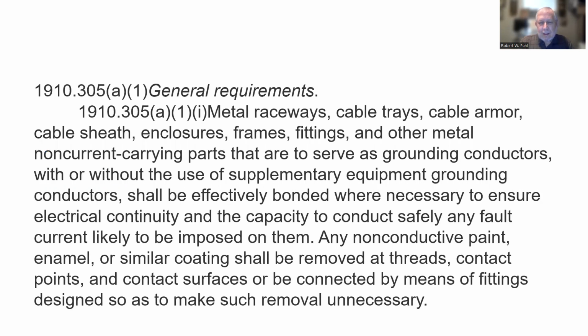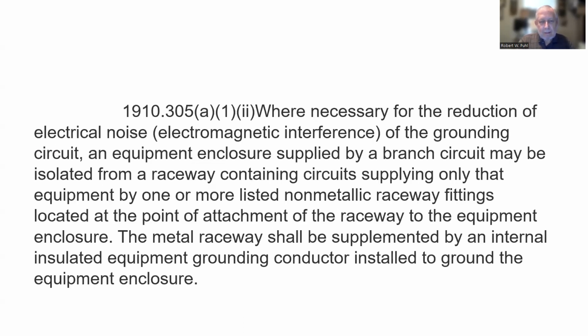General requirements: metal raceways, cable trays, cable armor, cable sheath enclosures, frames, fittings, and other metal non-current carrying parts that are to serve as grounding conductors, with or without the use of supplementary equipment. Grounding conductors shall be effectively bonded where necessary to ensure electrical continuity and the capacity to conduct safely any fault current likely to be imposed on them. Any non-conductive paint, enamel, or similar coating shall be removed at threads, contact points, and contact surfaces, or be connected by means of fittings designed so as to make such removal unnecessary. So what they're saying, bonded, and if it's bonded, it's really going to have a good contact.